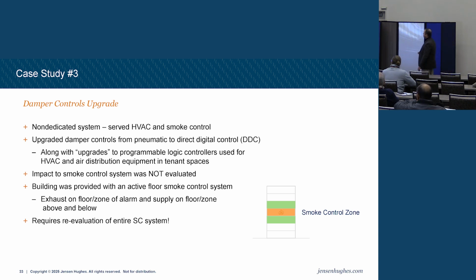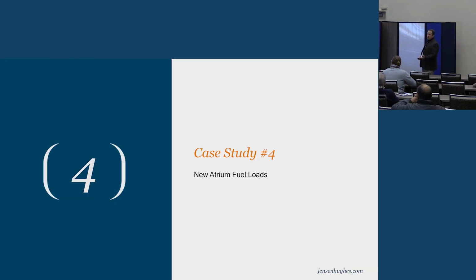The impact of smoke control was not evaluated, pretty common scenario. The building was provided with an active floor smoke control system, and the exhaust on the floor/zone of alarm and supply on the floor and the zone of alarm above and below requires reevaluation completely, and now I may no longer have my zones at all anymore because the system wasn't considered for that. So that's the big one.